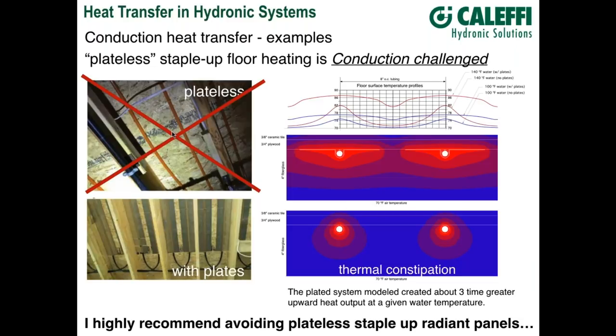Bob and I have probably spent 35 or 40 years collectively in our industry, and both of us — as well as many people viewing today — have seen these systems and seen some real disappointments with them. Conduction is important in a radiant floor or radiant panel system in general. Those aluminum plates are there to enhance conduction — they don't do much for convection, but they do a lot for conducting heat away from the tube and spreading it out across the floor.